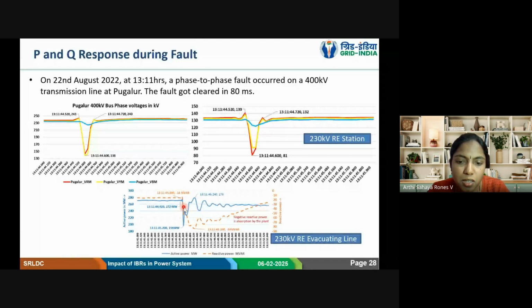In a few cases, the WTGs, usually the inverters, will trip on synchronization related issues, and the anti-islanding systems will maloperate. The anti-islanding scheme, which is designed to trip in case of loss of evacuating line, will maloperate during a transient fault in the grid. Due to that, some phase displacement protections will operate, tripping the inverters, WTGs, everything. Then we changed the angle and threshold for that. Sometimes due to transient variations, they will get tripped. Those kinds of things we have observed and changed.